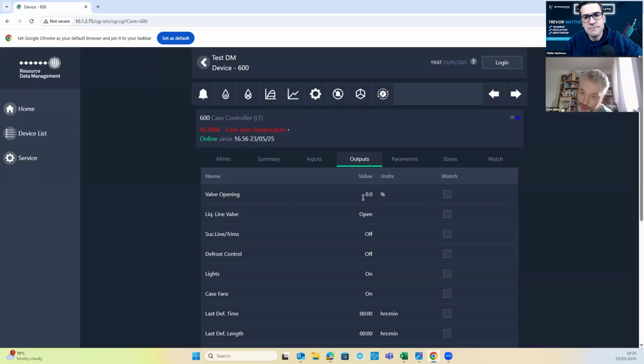RDM likes 4 to 20 milliamp transducers. There's a good reason why we use 4 to 20 milliamps, and that's to detect open line. If it goes to 0 milliamps because the line's open to the transducer, you'll get a fault. So I'm going to be checking to see if there's a reading on that. I'm not going to worry too much if it tells me when I come to set it up that there's a fault with the evaporating temperature, because RDM knows that you ain't going to operate this below the triple point. And I wouldn't be worried about the reliability of that reading until I've got pressure in it. What I'm just checking is that there is something there.